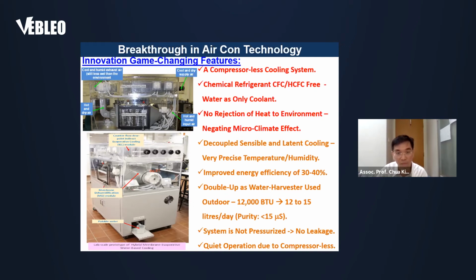Whereas now we are rejecting about 15% of a little bit of air, which is about 26 to 27 degrees, much more cooler. We can actually decouple the system, doing cooling and moisture removal separately. By decoupling it, you can evolve two different separate technologies.